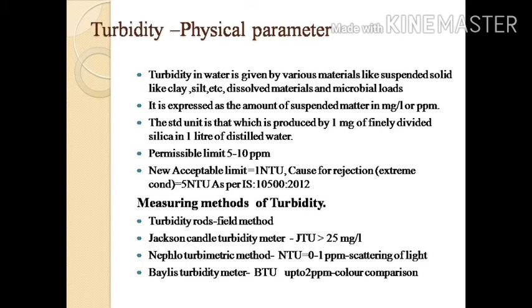The first method to measure turbidity is the turbidity rod. It consists of a graduated tape, a graduated aluminum rod, and a platinum needle. The graduated tape is provided on the top of the rod, and the graduated aluminum rod is provided at the bottom. At the bottom of the aluminum rod there is a platinum needle, and one end of the needle has a nickel ring. The dimension of the platinum needle is 1 mm. The length of the graduated aluminum rod is 20.3 centimeters. The length of the graduated tape is 12.2 centimeters.